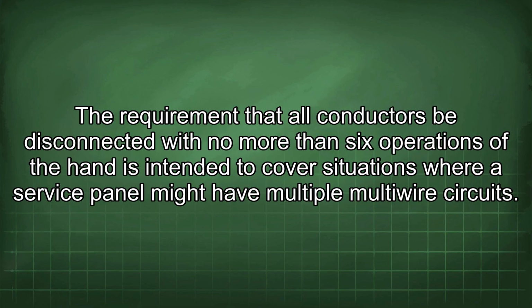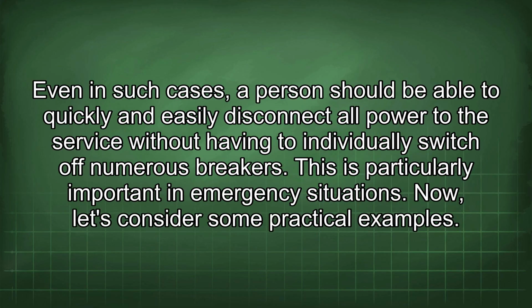The requirement that all conductors be disconnected with no more than six operations of the hand is intended to cover situations where a service panel might have multiple multi-wire circuits. Even in such cases, a person should be able to quickly and easily disconnect all power to the service without having to individually switch off numerous breakers. This is particularly important in emergency situations.